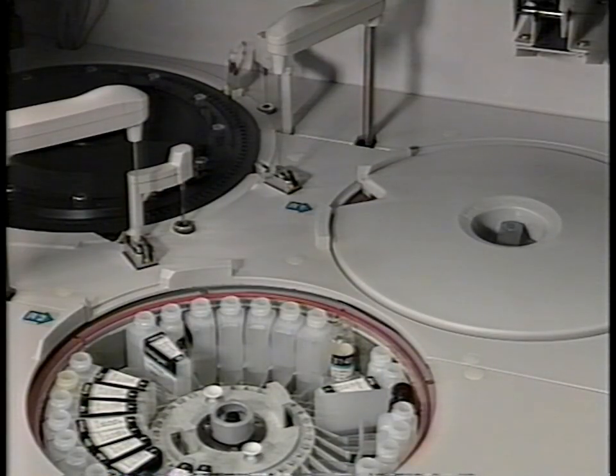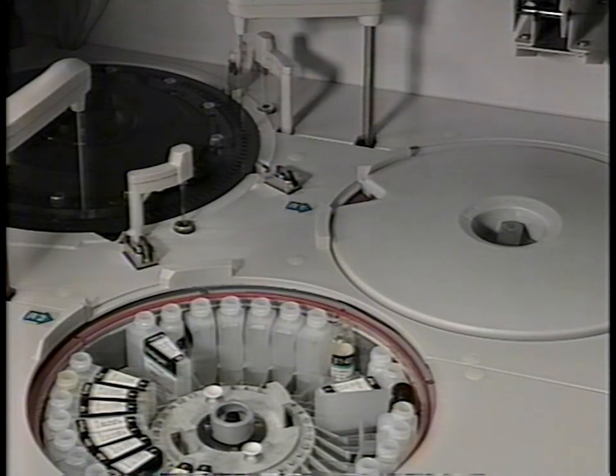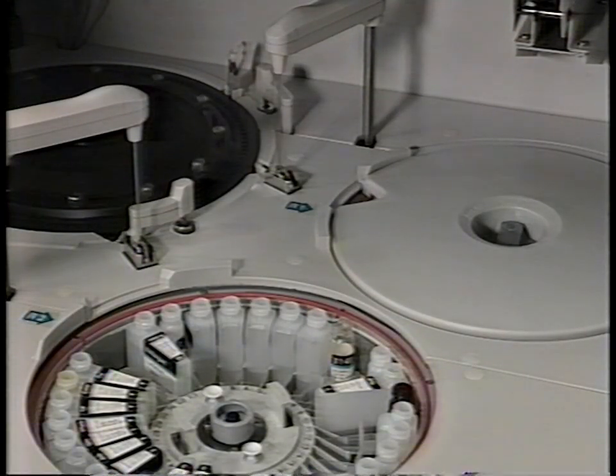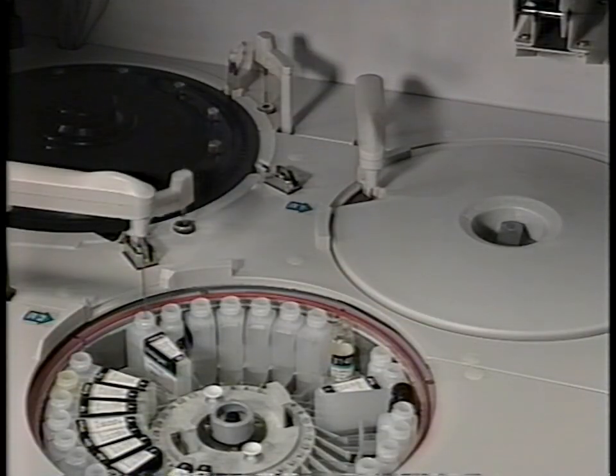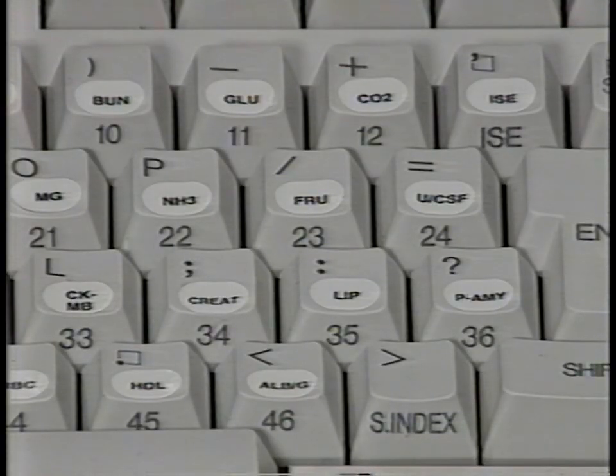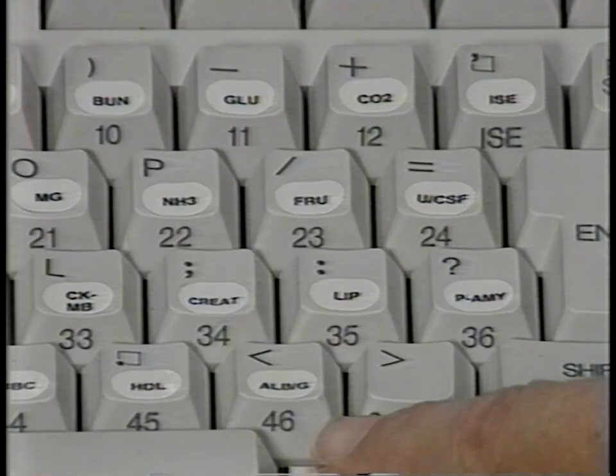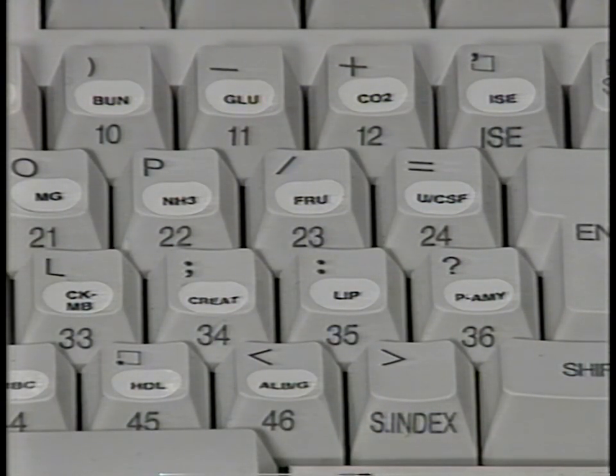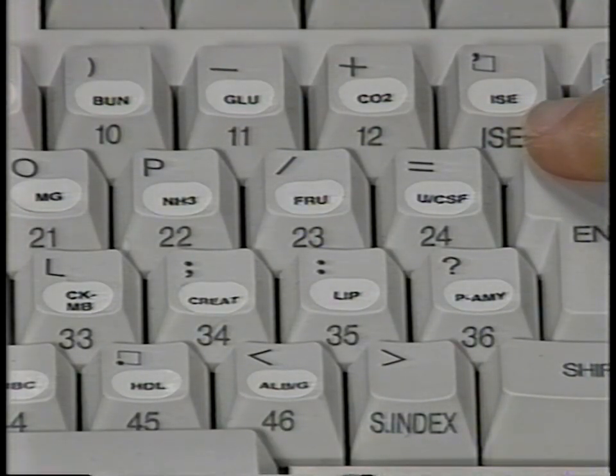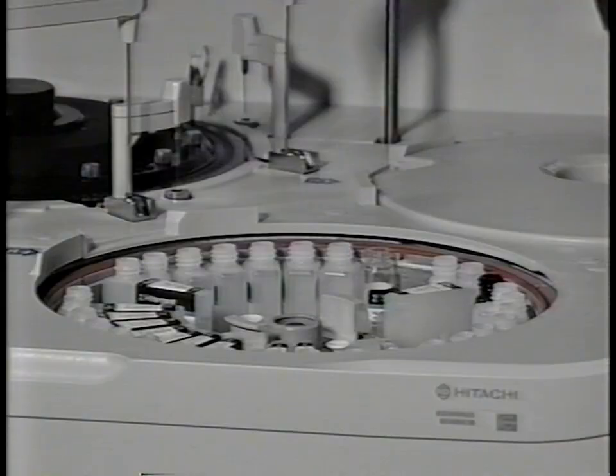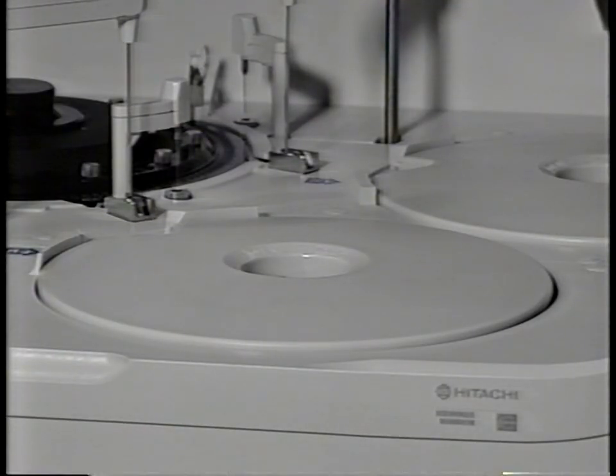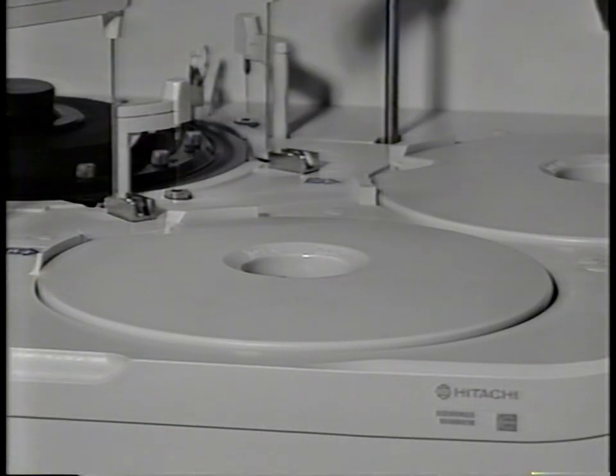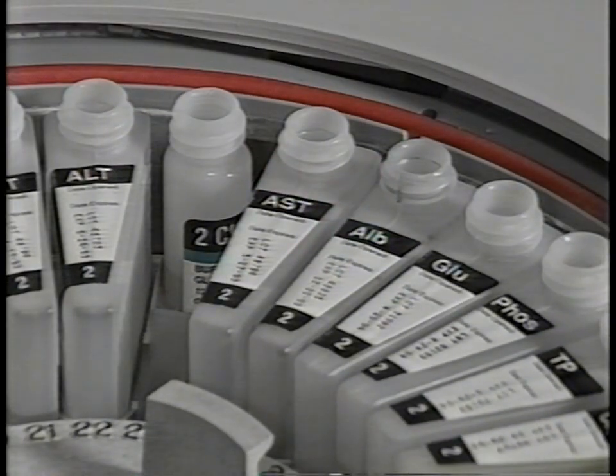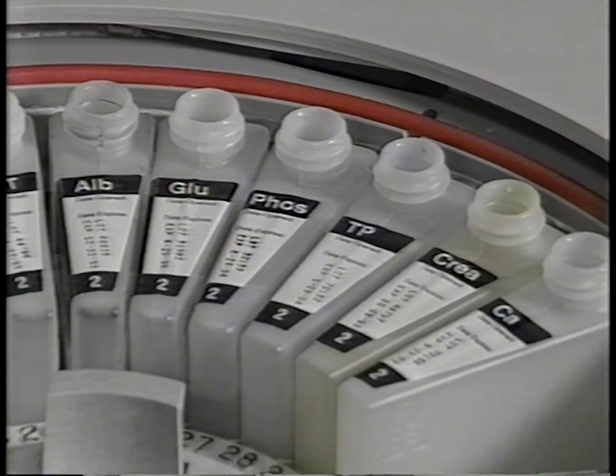As mentioned earlier, each reagent disc has 33 positions for reagent bottles, with one position on each disc reserved for Hitachi. One might assume, therefore, that the 911 is a 32-channel analyzer. However, if you look at the keyboard, you'll see test selection keys numbered from 1 to 46. The 911 can have parameters for 46 different chemistries in its memory, plus the 3 ISEs, sodium, potassium, and chloride. If a cover is removed and replaced during standby, the analyzer automatically performs a reagent registration process. By reading the barcode labels, it determines which reagents are on board and which tests can be run.